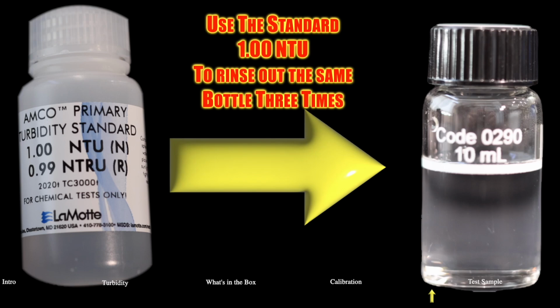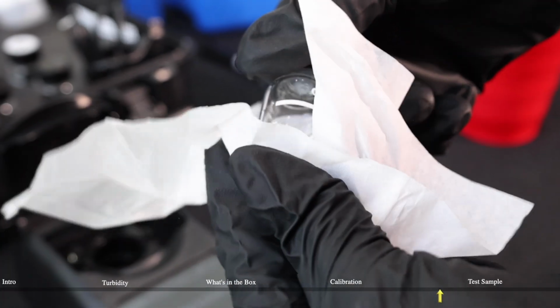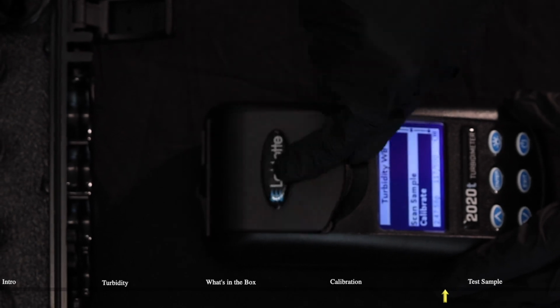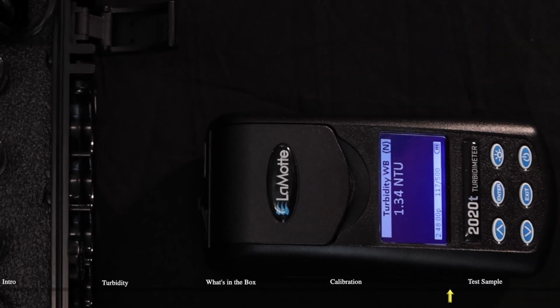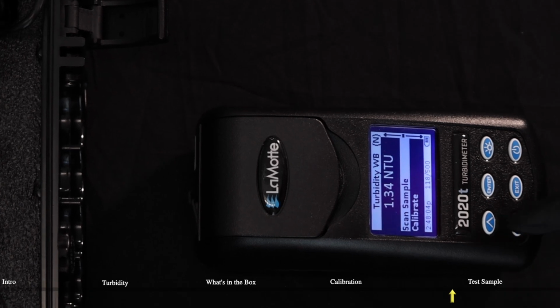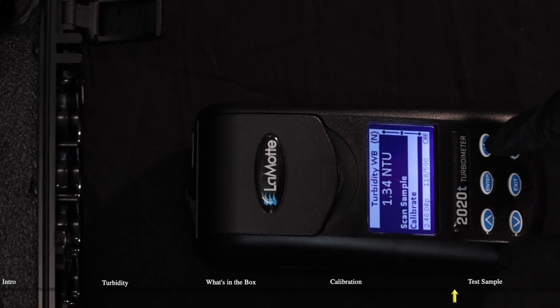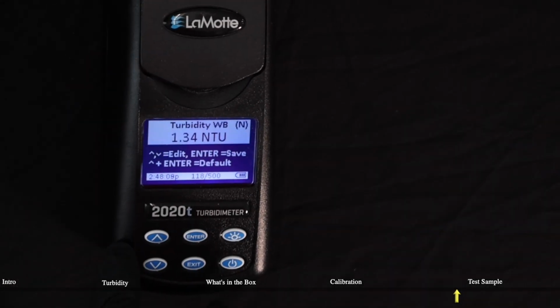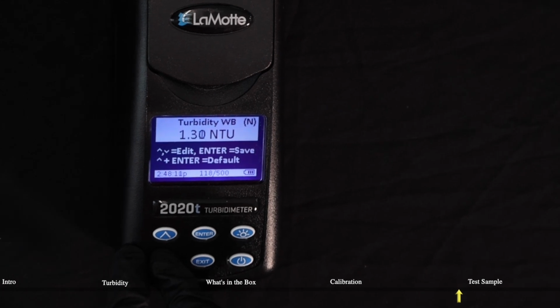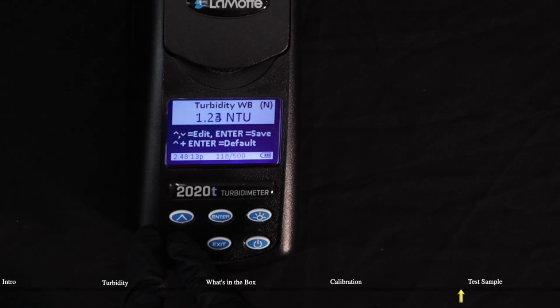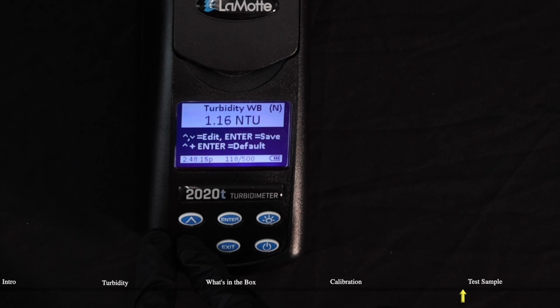Using the same rinsing method, you will fill up the same bottle with the 1 NTU standard fluid. Again, wipe the glass as clean as possible and insert it back into the meter. This time, you will press Enter to scan sample. Once the sample is scanned, use the up and down arrows to select Calibrate. Set the NTU to match the NTU standard you just filled the bottle with. Once it matches, hit Enter to select calibration and save it.